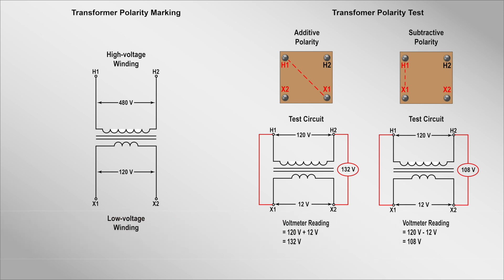Let's get started by discussing transformer polarity. What exactly is transformer polarity? Transformer polarity refers to the relative direction of the induced voltages between the high and low voltage terminals. Knowing this is essential in making three-phase and single-phase transformer connections. As you can see in the drawing, H1 and H2 are the high voltage windings, and X1 and X2 are the low voltage windings.